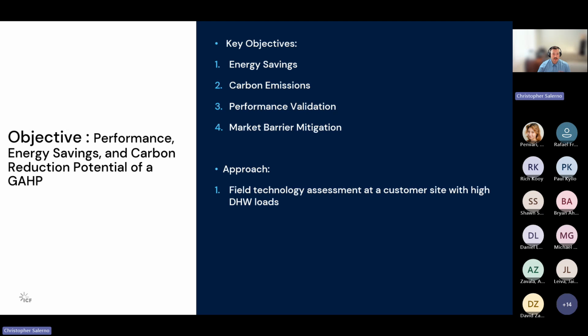The fourth would be market barrier mitigation. We want to be able to address the barriers that we found throughout the project and to be able to minimize those and increase adoption of this. Our approach really was, as mentioned before, this field study, which was a field technology assessment at the customer site, specifically a site with really high domestic hot water needs. And we'll go into that. It is very important that these systems be used where the gas-fired heat pump is running as much as it can to be able to base load, and so it reaches high efficiency performance, and so you're at the end of the day making the system more efficient. And so we target places with high DHW loads.